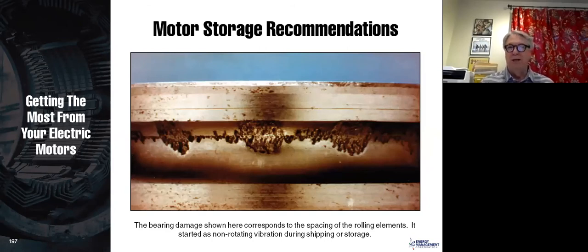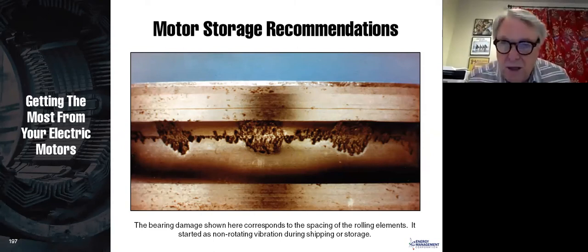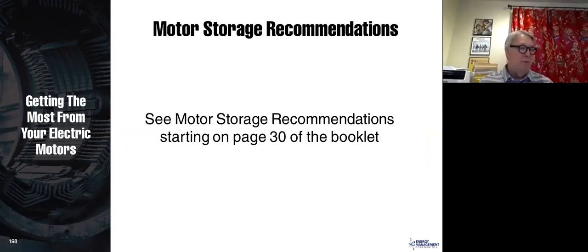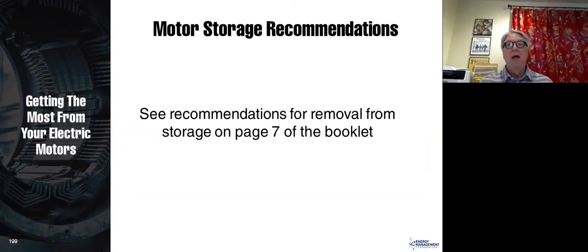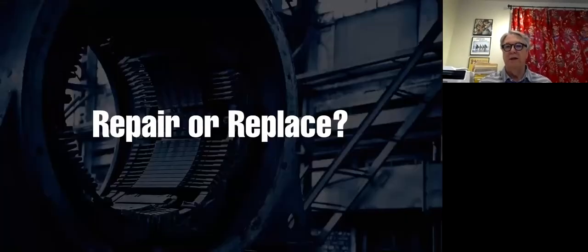In your booklet. This is a brand new motor that was stored and it wasn't rotated, and those are the marks left by the ball bearings because of vibration. There was a train running by that motor storage facility. So motors need to be stored properly, and on page 30, it will tell you all the information you need to know about properly storing a motor. And when you're going to remove it from storage and put it back into service, page 7 gives you all the procedures for doing that.